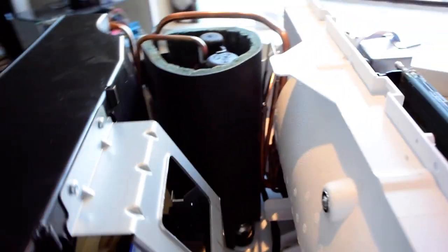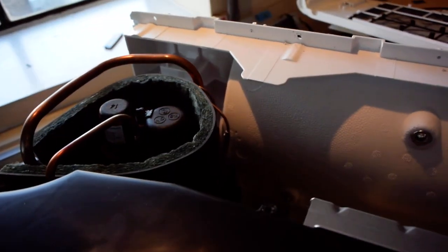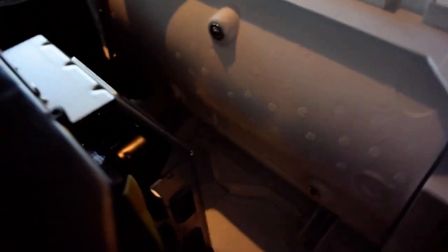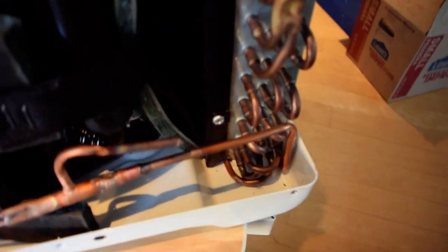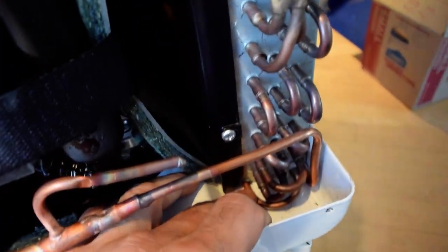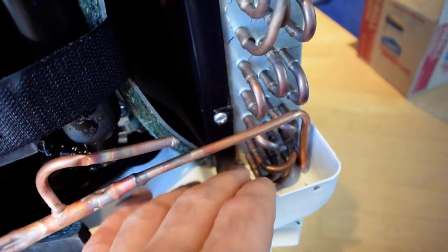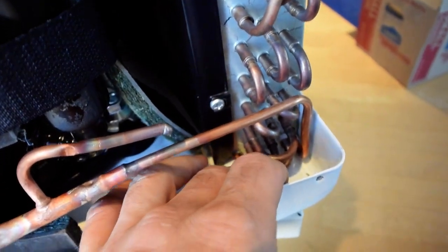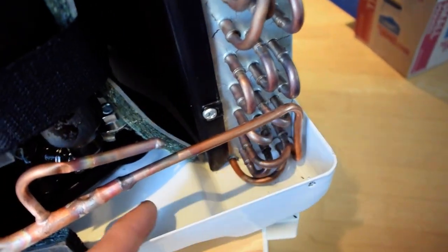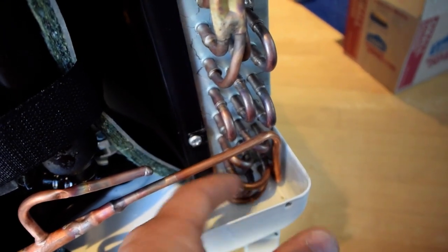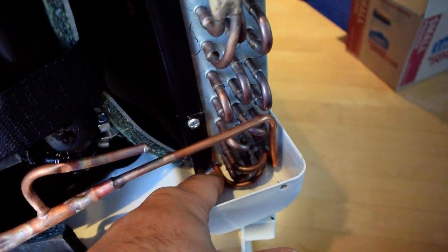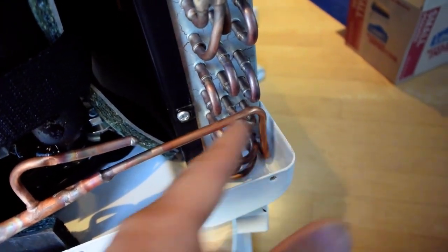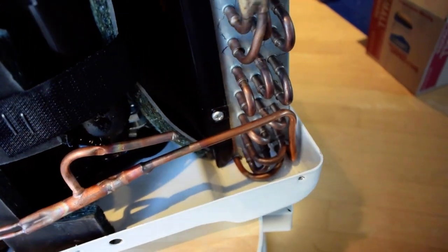Some other interesting features on here probably not related to noise control are the subcooling that happens here. So this bottom part of the condensing coil is sitting in this tray and the condensate is sitting in there. So that subcools the liquid before it goes back into the evaporator.